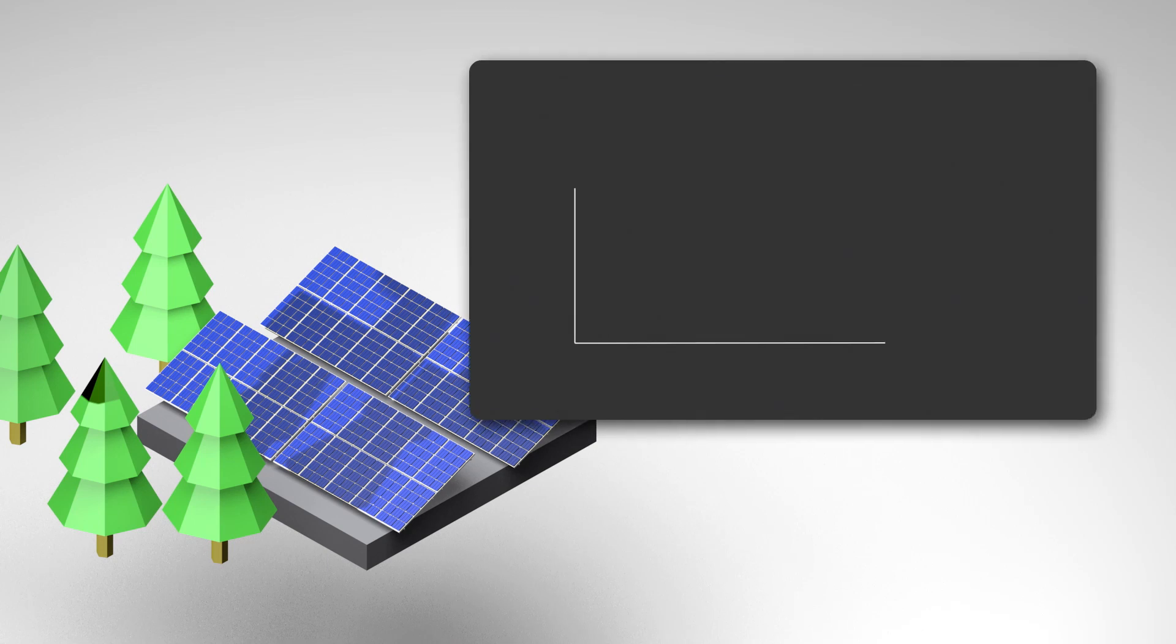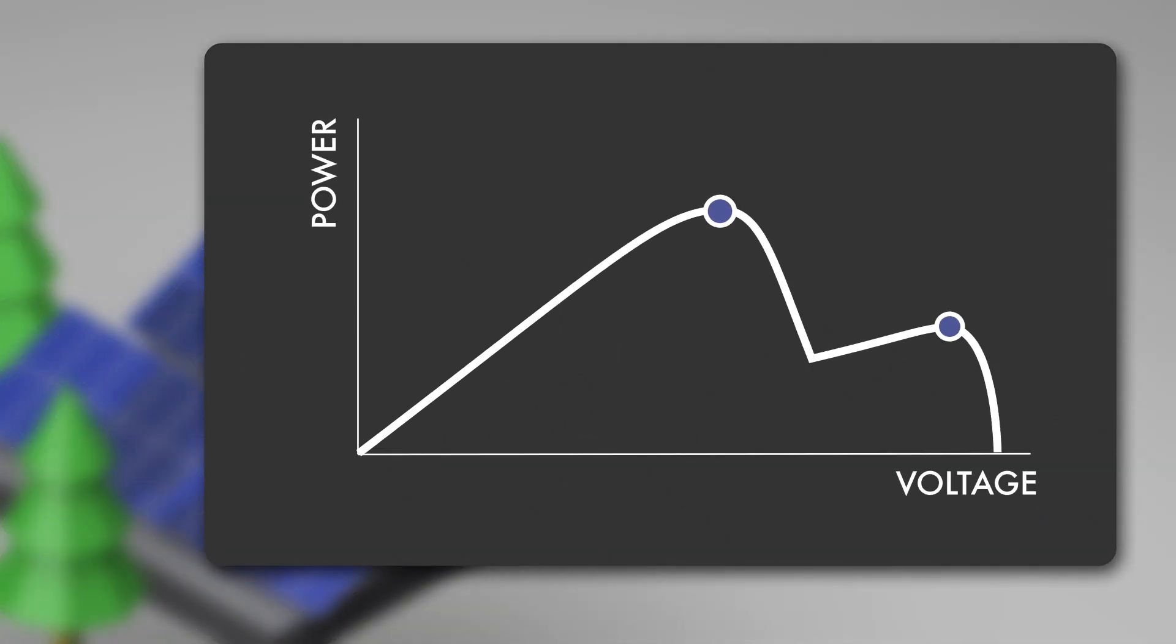In case of shading, the power curve of the PV array changes. It now has several peaks, but not all of them will be found by conventional MPP trackers because they only scan the near range of their current operating point. Consequently, the output of the PV system can be significantly lower than it should be due to the shading.